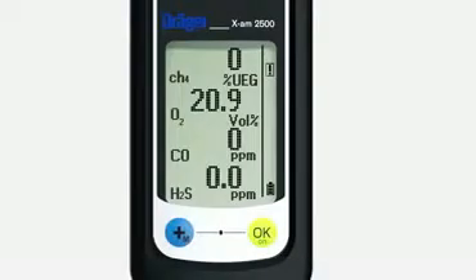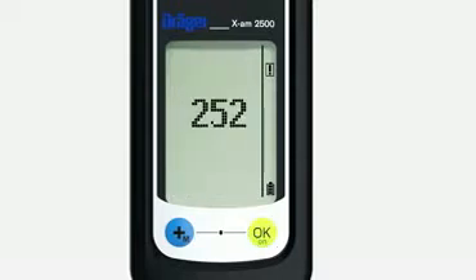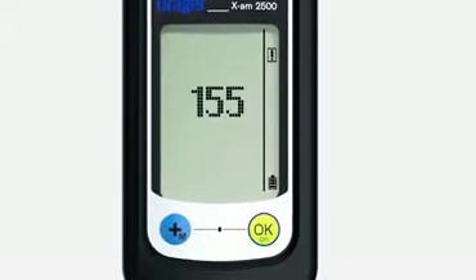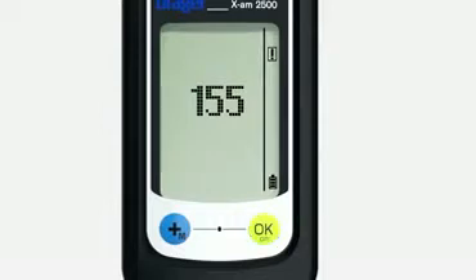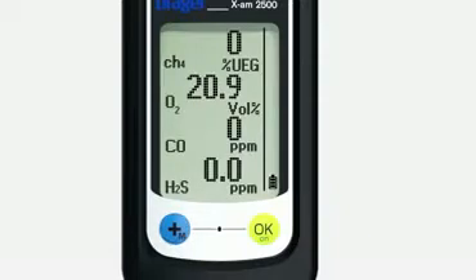The exclamation mark on the right is used for information. Press and hold the OK key for 3 seconds. An information code is then displayed. The list of information codes is contained in the technical manual posted on the product webpage at www.draeger.com. By pressing the OK key again, additional information codes may be shown. To abort, press the plus key to return the device to measuring mode.